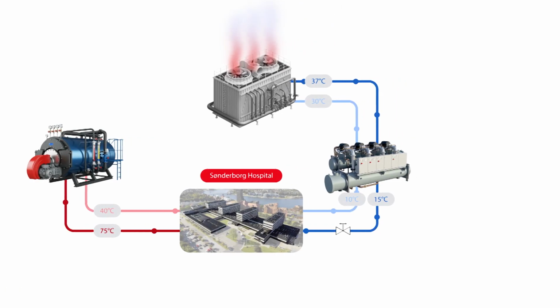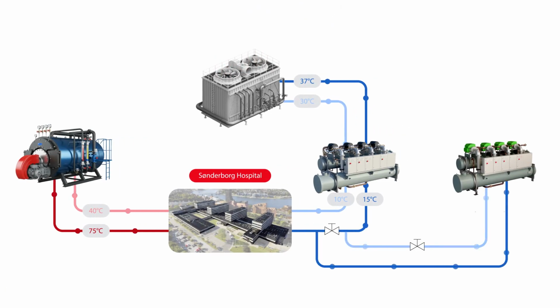To tap into the hospital's unused thermal potential, a water-to-water heat pump was installed to replace the gas boilers and separate cooling systems, with chillers kept as minimal use backup. The water-to-water heat pump's cold side is tied into the existing chilled water network, continuing to deliver the same cooling temperatures required for comfort cooling and for sensitive equipment such as MRI and CT scanners.